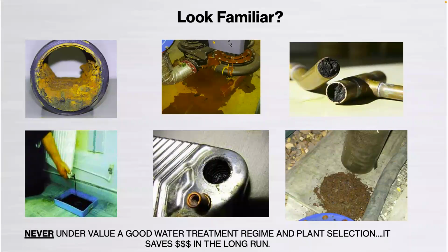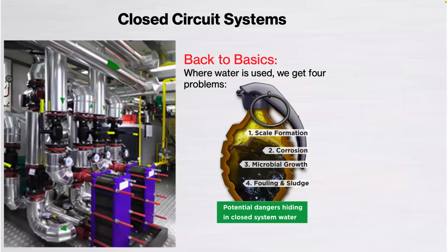So I appreciate that, if you're looking at designs, you pass it down, and ultimately the contractor, no doubt, will take responsibility for the cleaning of the system. But it's really important that there's a good, hard, solid specification put to the contractor of the expectations of proving good velocity around that system, protecting terminal units, and so forth, and witnessing throughout various parts of the project.